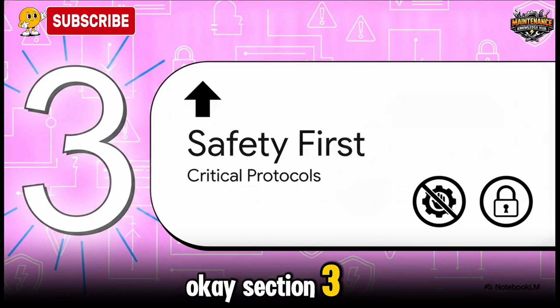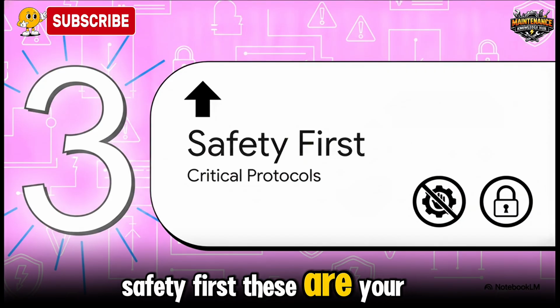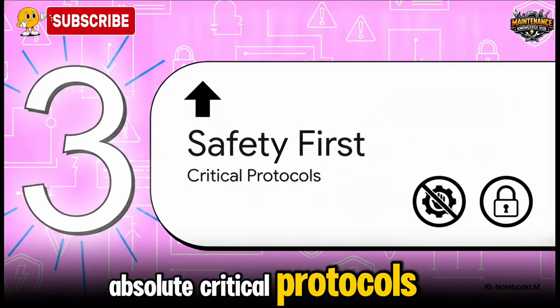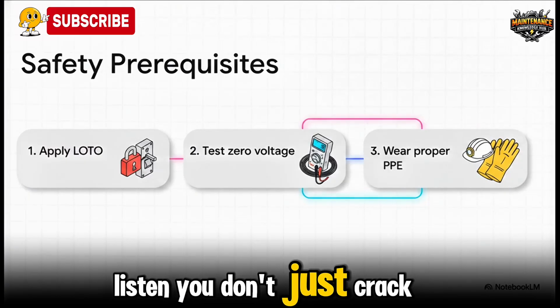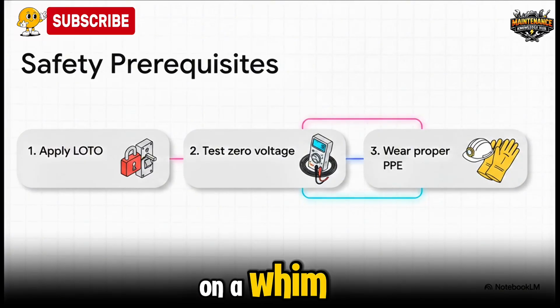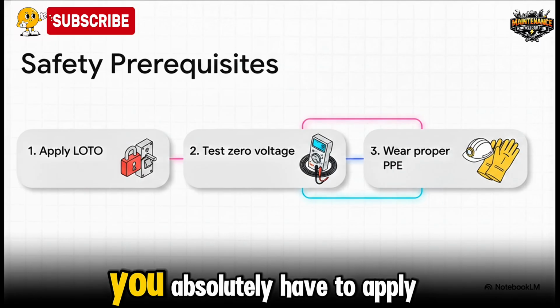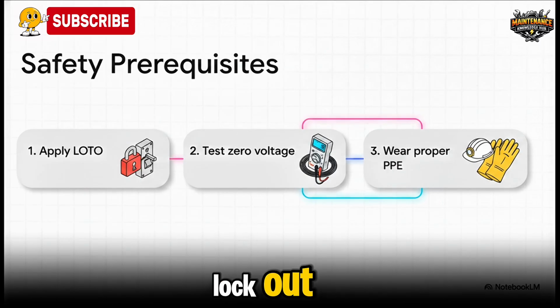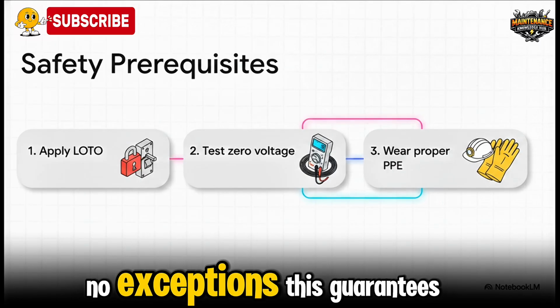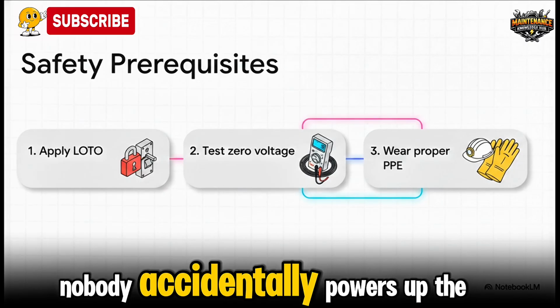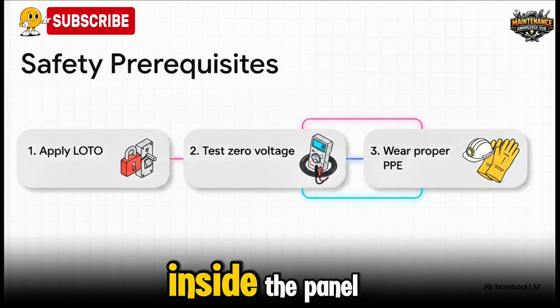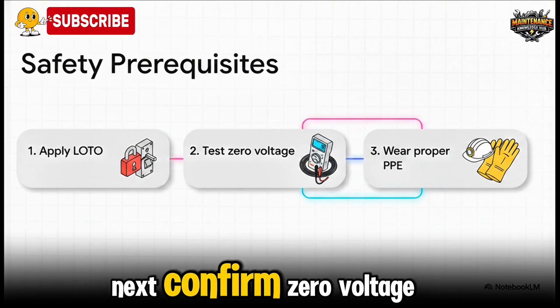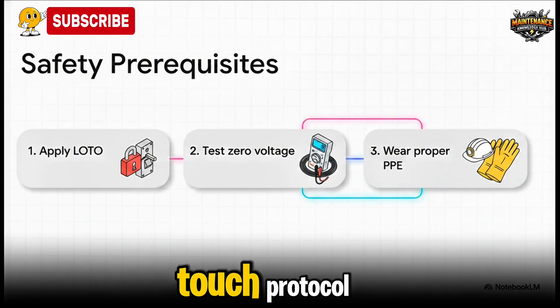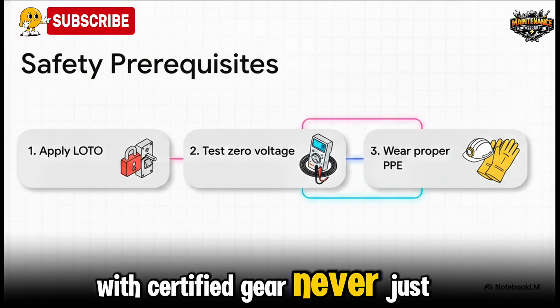Okay, Section 3, safety first. These are your absolute critical protocols. Listen, you don't just crack open an 11 kV VCB on a whim. Before any maintenance even begins, you absolutely have to apply lockout-tagout, LOTO. No exceptions. This guarantees nobody accidentally powers up the system while your hands are literally inside the panel. Next, confirm zero voltage. Use a strict test before touch protocol with certified gear. Never just assume it's dead.